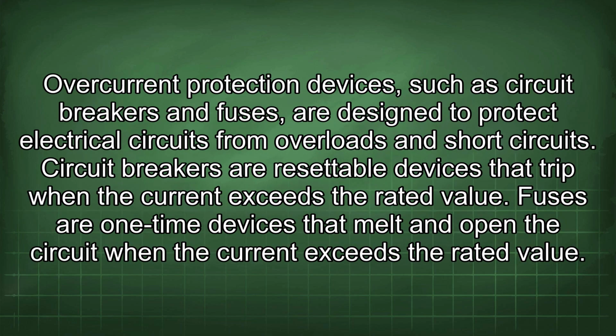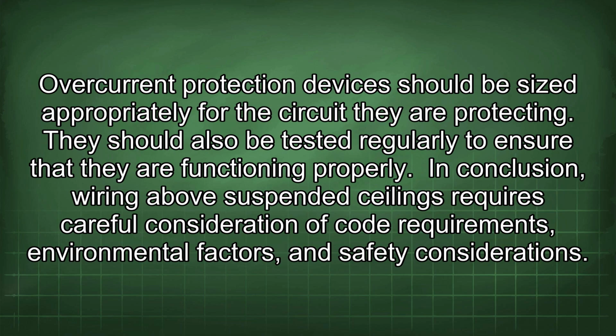Overcurrent protection devices such as circuit breakers and fuses are designed to protect electrical circuits from overloads and short circuits. Circuit breakers are resettable devices that trip when the current exceeds the rated value. Fuses are one-time devices that melt and open the circuit when the current exceeds the rated value. Overcurrent protection devices should be sized appropriately for the circuit they are protecting. They should also be tested regularly to ensure that they are functioning properly.